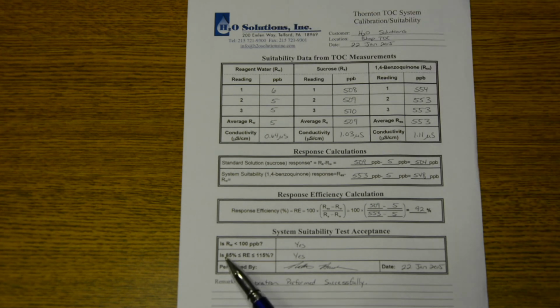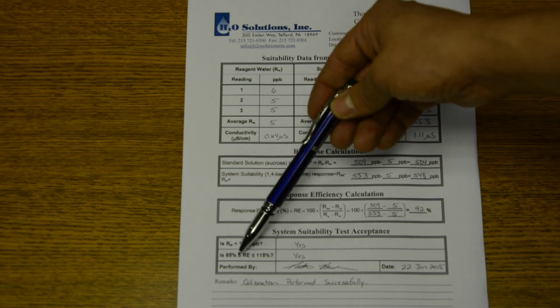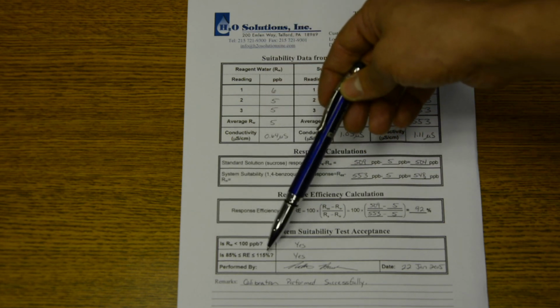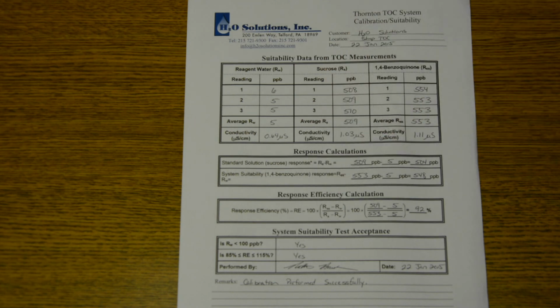And then is the efficiency calculation greater than 85% and lower than 115%? If it was, then yes, and it passed the suitability test. If it's below 85%, if it's 84 or below, or if it's 116 and above, then it didn't pass the suitability response efficiency test, and either the meter itself may need to be replaced, the sensor may need to be replaced, or the calibration may need to be redone because it's not reading properly.